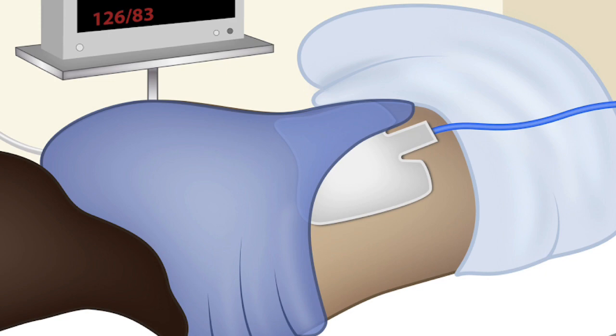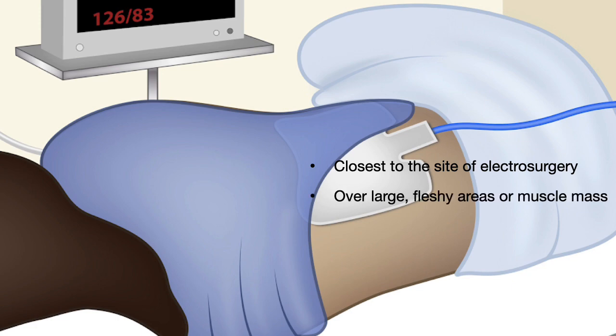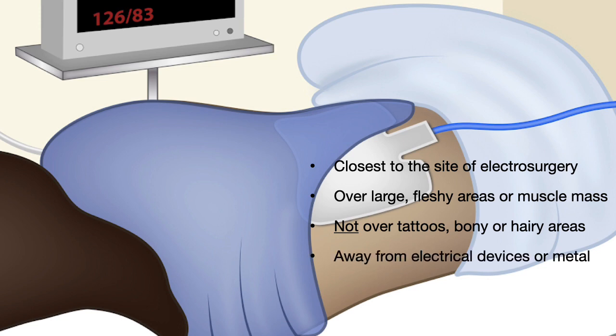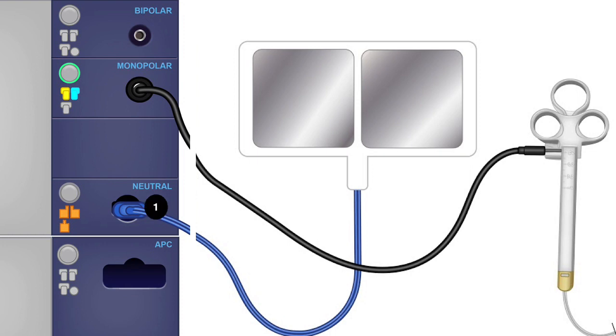It is typically applied in the loin, where you have a lot of muscle that is closest to the site of electrosurgery, and typically applied over a large fleshy area or a muscle mass. Avoid putting it on a bony surface, and also avoid tattoos, avoid hairy areas, and stay away from electrical devices or any metal. So these are the principles to keep in mind when you apply the dispersive pad. And then you take the electrode and plug it into the neutral socket, and then to the monopolar socket you plug in another electrode that goes to the snare.